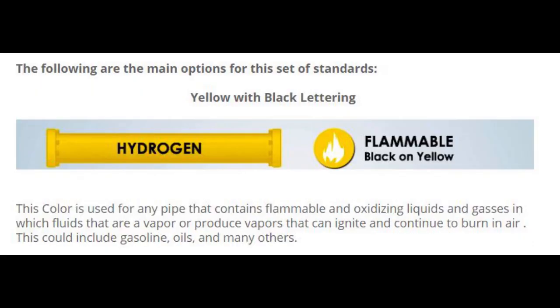Yellow with black lettering: This color is used for any pipe that contains flammable and oxidizing liquids and gases — fluids that are vapor or produce vapors that can ignite and continue to burn in air. This could include gasoline, oils, and many others.